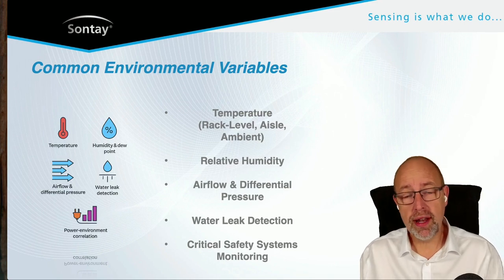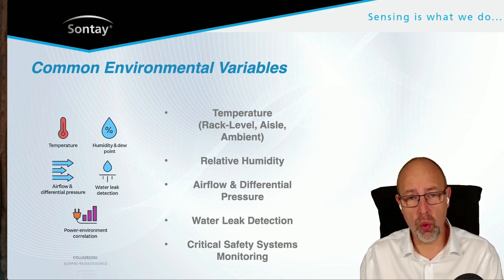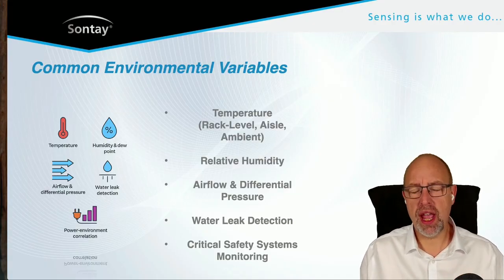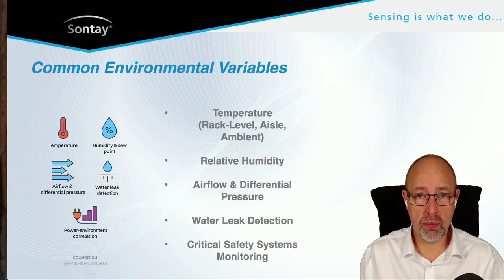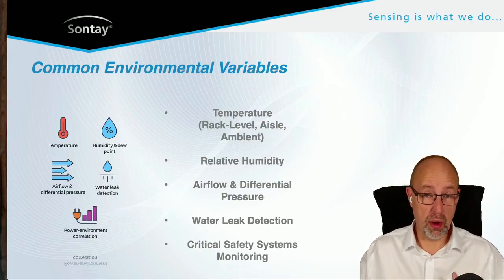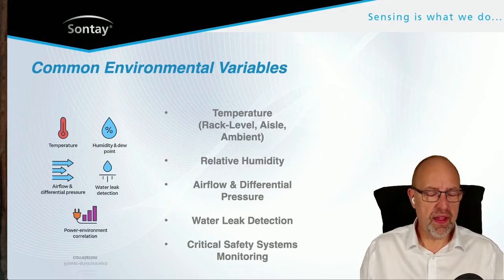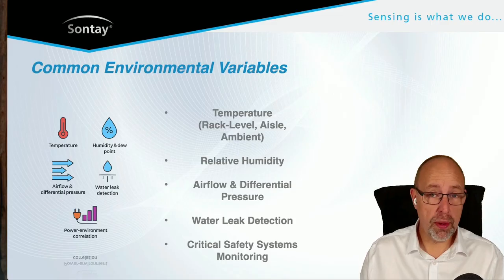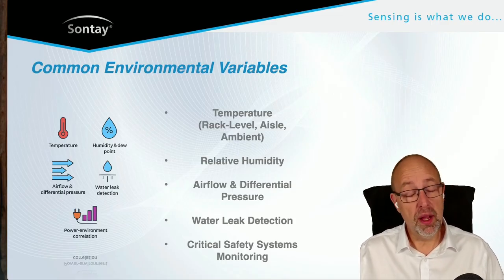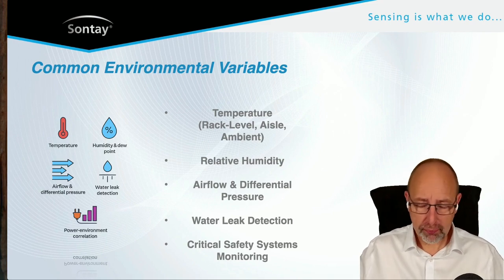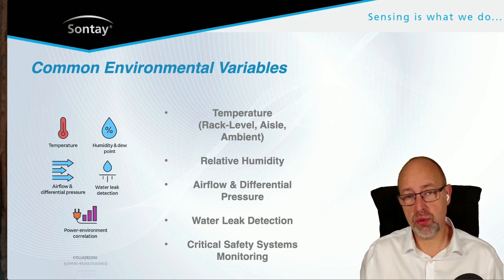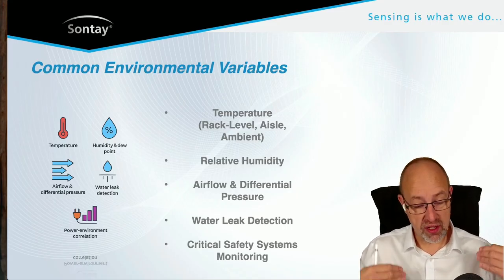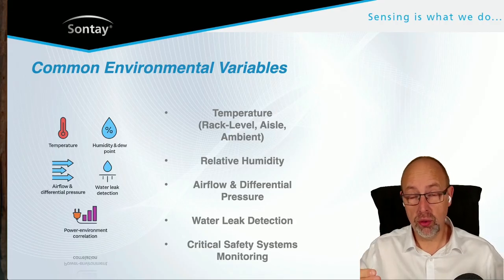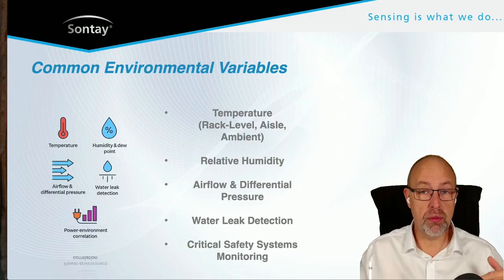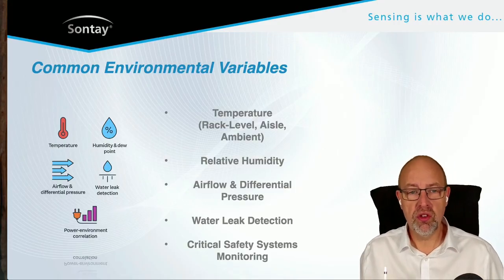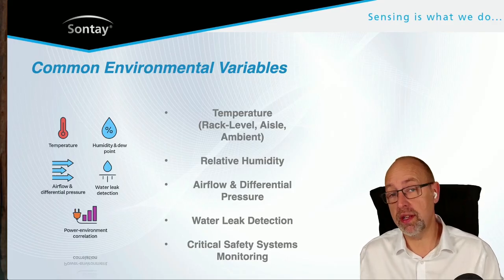As I mentioned as well, relative humidity, certainly in the data hall itself, is important. When we are adding fresh air into a commercial office building which is populated with people, we need to provide enough fresh air for those people to be able to breathe easily and function normally at work. There's a much lower requirement for ventilation in a data center because there's no people. You still need to change the air in there, because otherwise it would get very stale, but you don't need as much fresh air. Because of that, the air tends to be recirculated much more in a data center. It strips the moisture out. We're cooling this. When we cool it, the moisture in the air condenses on the cooling coils, and that drains away. Obviously, the absolute humidity, and then the relative humidity as a result comes down. So we often have to monitor the relative humidity, and then quite often with data centers actually add humidity in there.